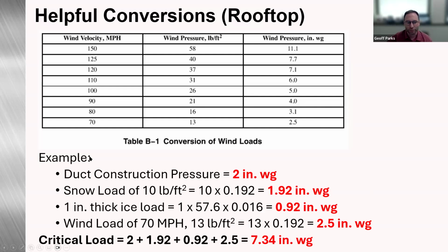So what you can do is, for this example, say our base duct construction standard pressure, we're constructing at 2-inch water gauge, and you're working on a roof in an area that has a snow load of 10 pounds per square foot. So that equated to 1.92-inch water gauge. If you had ice, we did this math already, it was 0.92, and then we throw a wind load in there, and that equates to 2.5 inches. That's from up here, and also doing the math. So our critical load for this example would be 7.34 inches of water gauge.